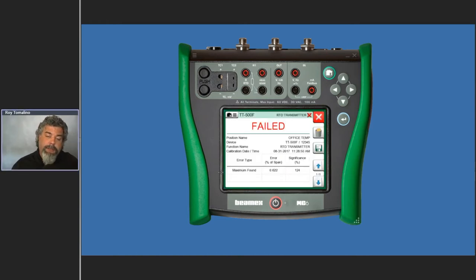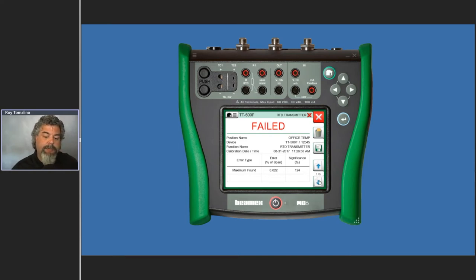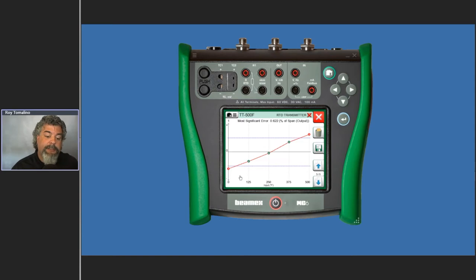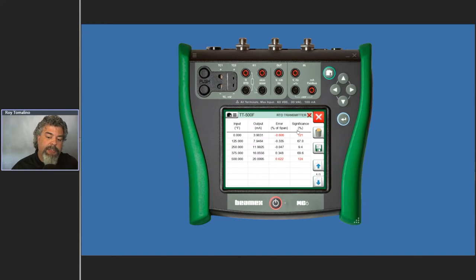The result is not looking so good — we're going to find out why. Our midpoint is fine, but there's something up with the zero and the span. So it failed. I'm going to save this as-found because this is a reflection on how this thing is set up, not a reflection on me as a technician. Here are the numbers in red, showing where it failed — the failure occurred at the zero and the span.